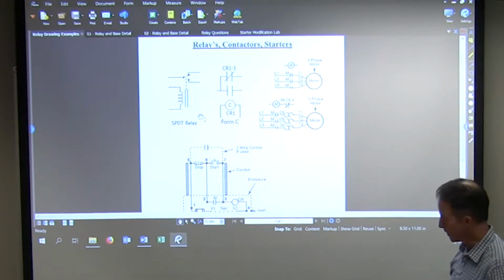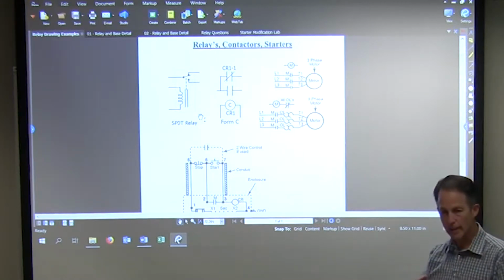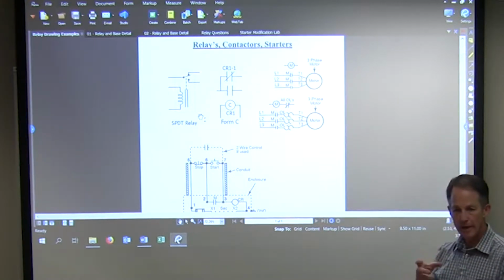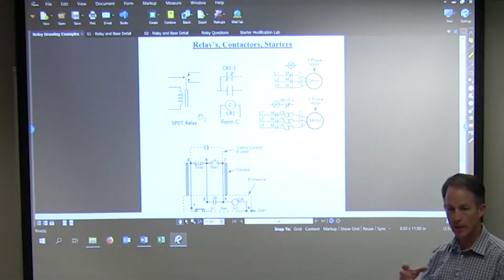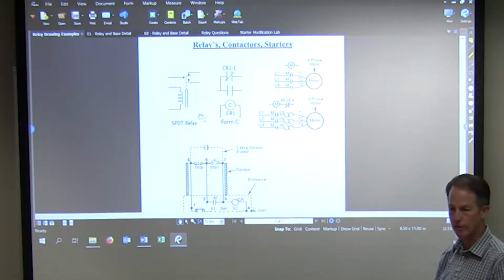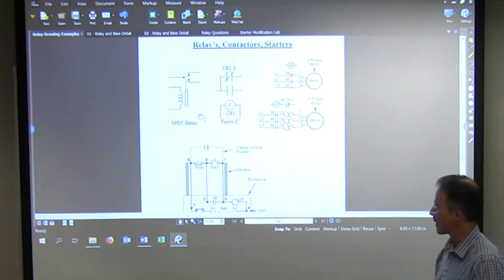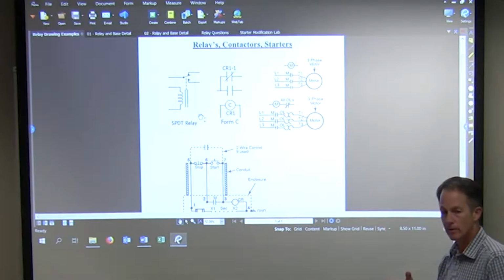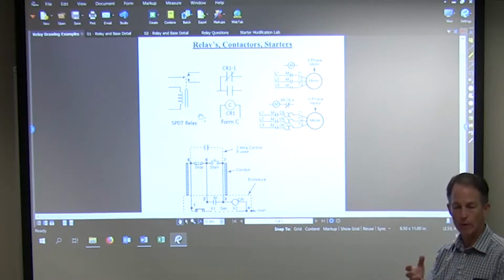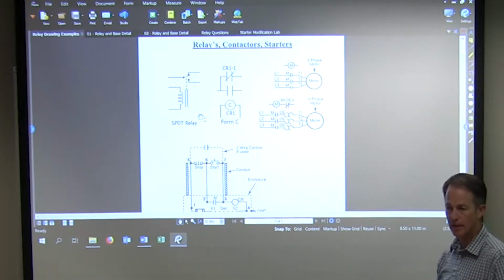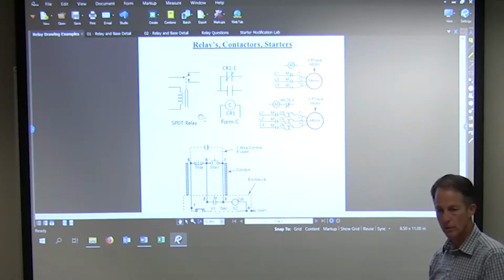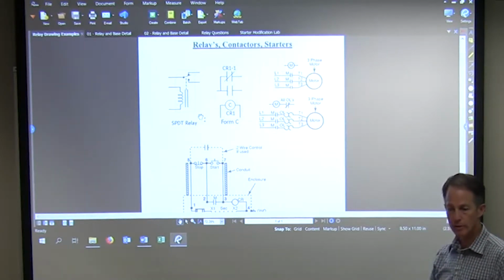So, with relays, they're pretty basic, right? I think most of us have worked with a single relay or maybe even a couple of relays at a time, and that's not too hard to troubleshoot and figure out what's going on. How do I troubleshoot a coil of a relay versus a contact? If I have a meter, what are some things I can do to see if a coil is working correctly?